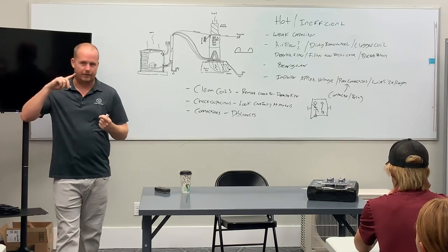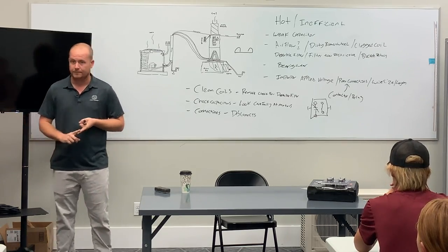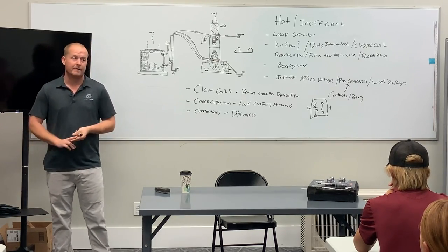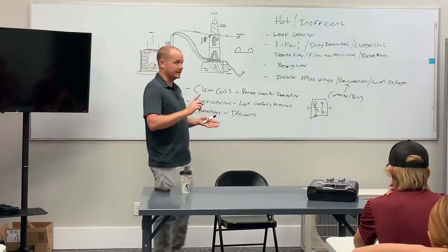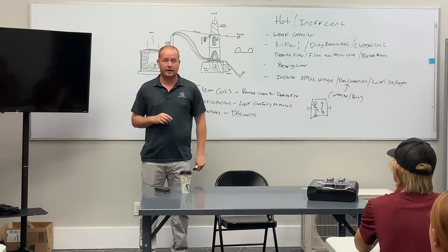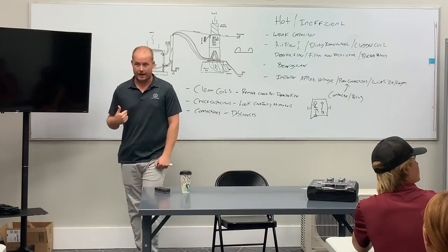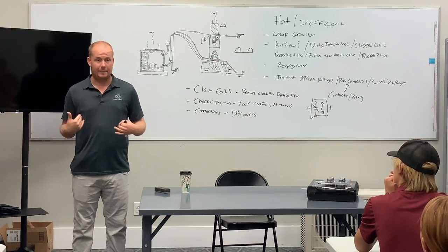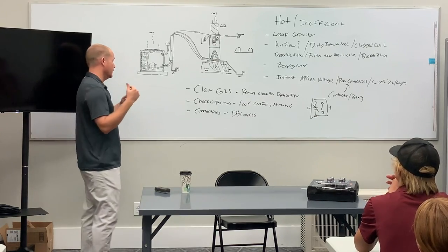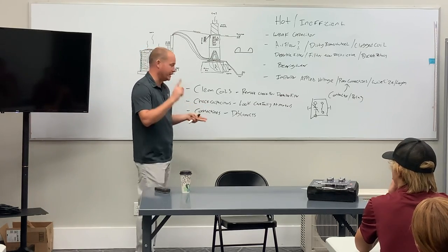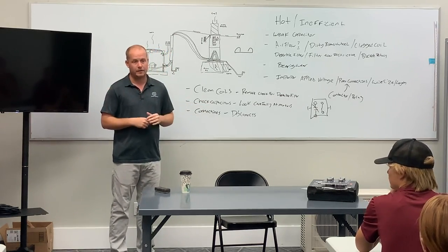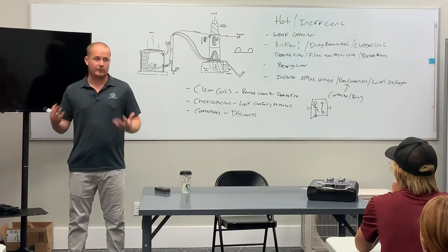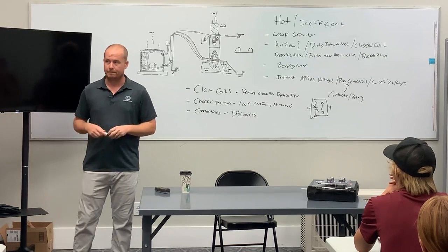So doing things like washing coils really well when they need it. Doing things like, we talked about in terms of maintenance, cleaning the bottoms out of condenser coils. Doing things like fixing wire abrasions. Doing things like whips that are improperly done or disconnects that are coming off the wall, taking care of that. Insulation pulling off of air handler panels, fastening that better, taping it in place, checking float switches, checking capacitors. Those are all things that add value. Because our goal is to prevent that system from failing, number one, and number two, to keep it running efficiently so that the power bills aren't going up.